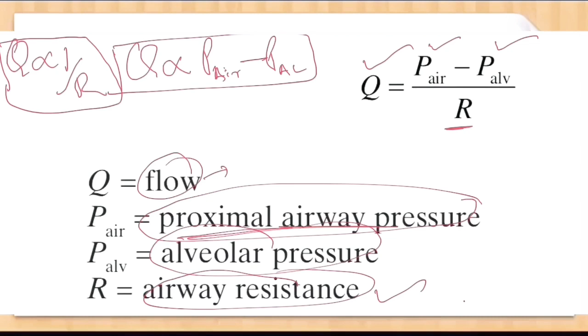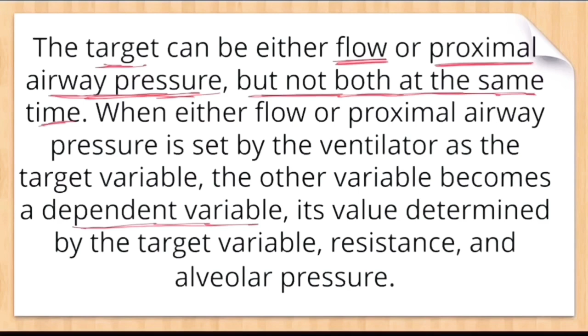The target can be either flow or proximal airway pressure, but not both at the same time. So you cannot set the ventilator both flow targeted and proximal airway pressure targeted. When either flow or proximal airway pressure is set by the ventilator as target variable, as I said, the other variables become the dependent variable. Okay, like its value is determined by target variable, resistance, and alveolar pressure.